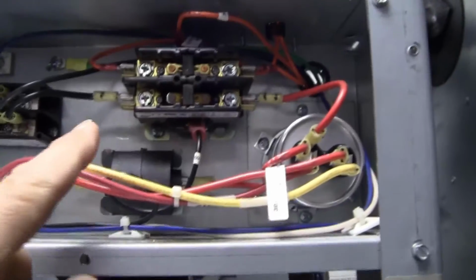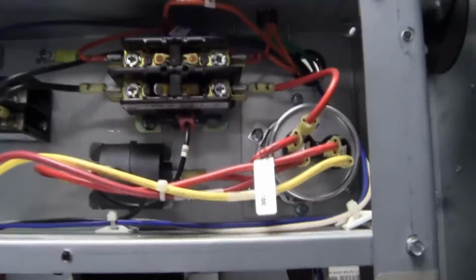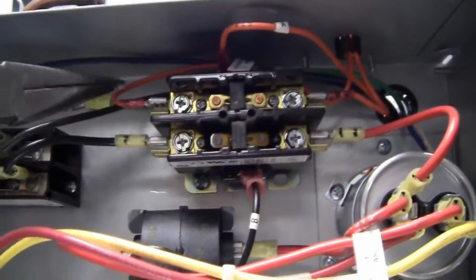Okay, a couple of things I do to make my life a little bit easier when I go to do this job is that I just took a black Sharpie and gave this one notch down here, one notch down here on the left-hand side of the contactor. On the right-hand side of the contactor, I took my leads that are connected here and here and gave them 2 notches on the top terminal and 2 notches here on the bottom terminal, just to label them. I also took my Ideal book here, which is for labeling electrical conduit and electrical stuff, and I just have an ABC book here. So I just labeled the coil terminals with the top one being A and the bottom one being B right there. A little hard to see on the camera, but that's B right there.